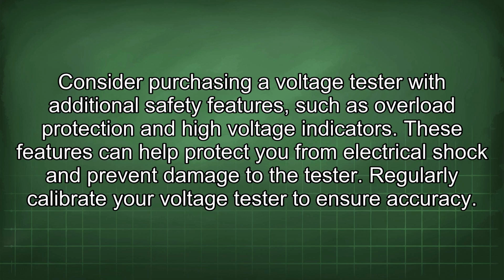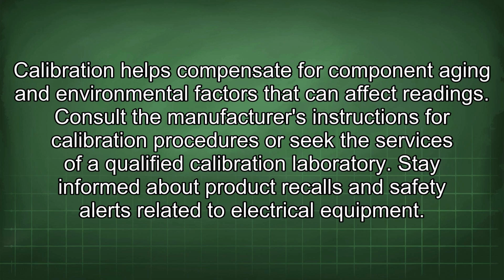These features can help protect you from electrical shock and prevent damage to the tester. Regularly calibrate your voltage tester to ensure accuracy. Calibration helps compensate for component aging and environmental factors that can affect readings. Consult the manufacturer's instructions for calibration procedures or seek the services of a qualified calibration laboratory.